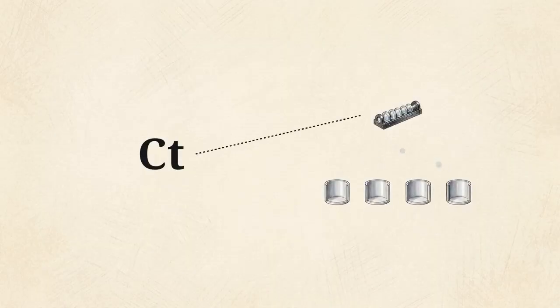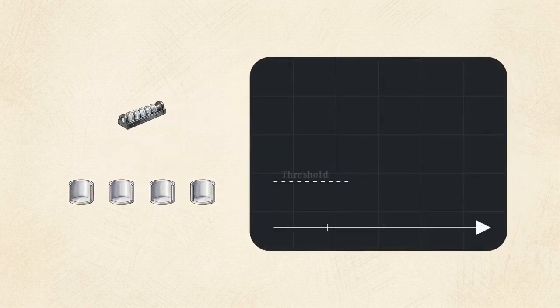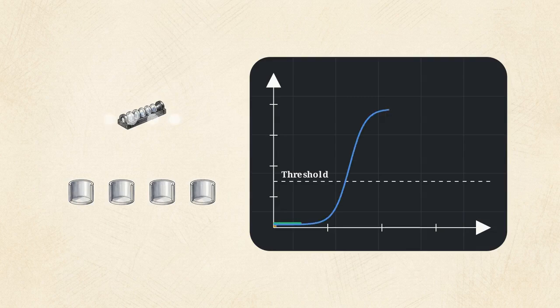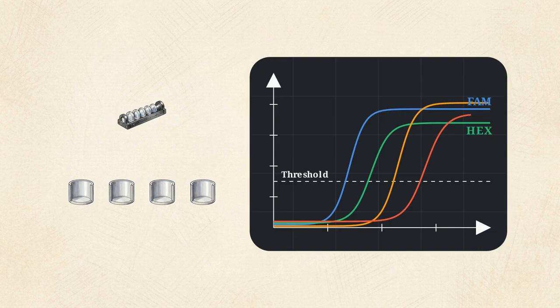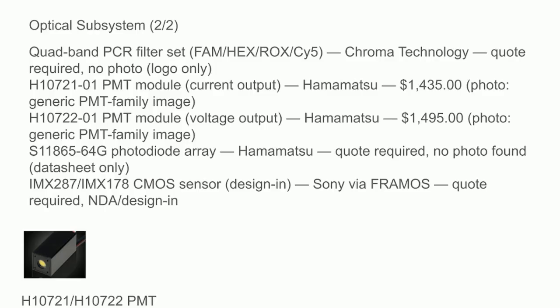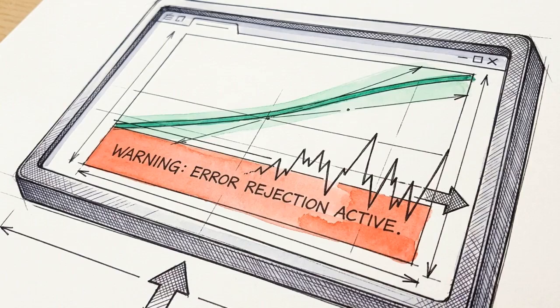Moving to the optical subsystem, calculating the exact threshold cycle, or CT, imposes an equally strict hardware demand. The sensors have to accurately plot the fluorescence of very low-abundance human transcripts across multiple dye wavelengths, including FAM, HEX, ROX, and Cy5. Cheaper photodiode arrays produce too much noise. The device requires highly sensitive, low background readings to establish a clean baseline.